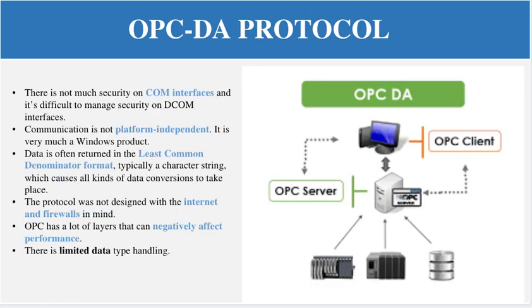OPC DA is based on the COM structure or COM interface, and it is difficult to manage security on COM interfaces. The communication is not platform-independent — it is very much a Windows product. Data is often written in the least common denominator format, typically a character string, which causes all kinds of data conversions to take place. The protocol was not designed with the internet and firewalls in mind. OPC also has a lot of layers that can negatively affect performance, and there is limited data type handling.